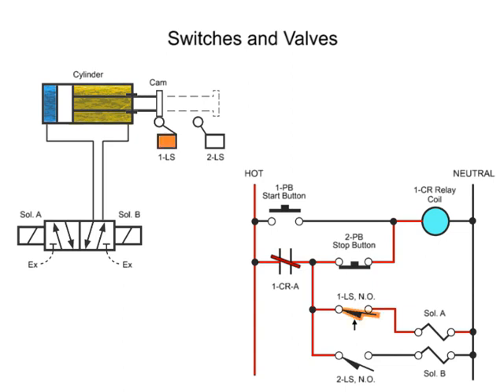Since limit switch 1LS is held closed by the cam prior to the beginning of the cycle, current flows through this switch and activates solenoid A. Since limit switch 2LS is open prior to the beginning of the cycle, current cannot flow and thus solenoid B remains de-energized.